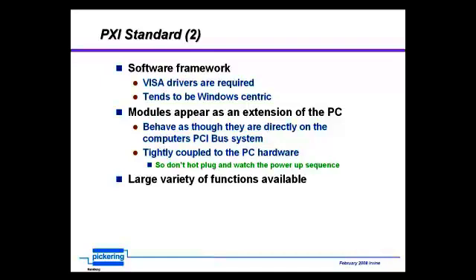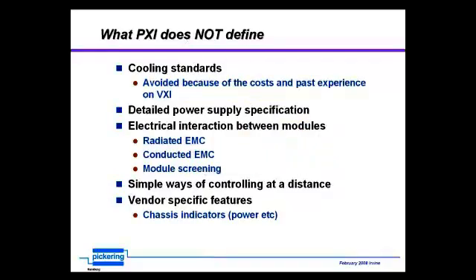The standard itself has got a huge number of different modules available — from switching through to instrumentation and data acquisition. Things that PXI doesn't define include cooling standards. The PXI standard does have a minimum expected dissipation per slot, but it's not very explicit about cooling pressures and cooling volumes. It's got a fairly detailed power supply specification, but it doesn't define everything. It also doesn't control electrical interaction between modules, like radiated EMC, conducted EMC, or module screening.